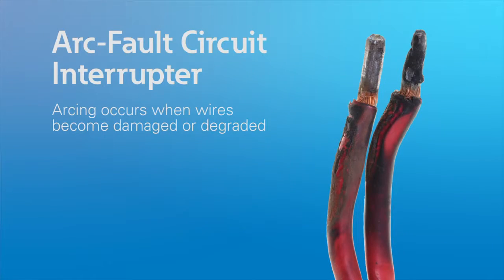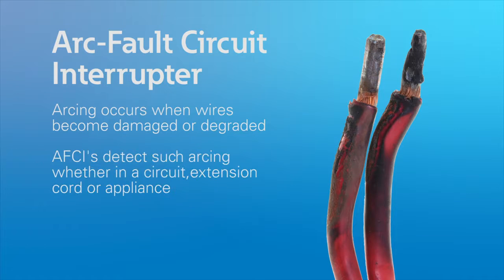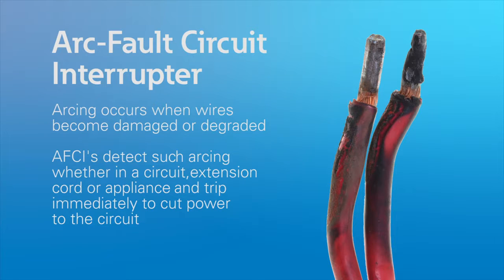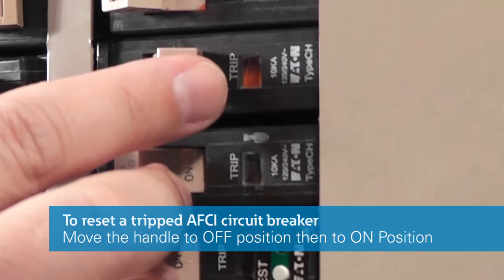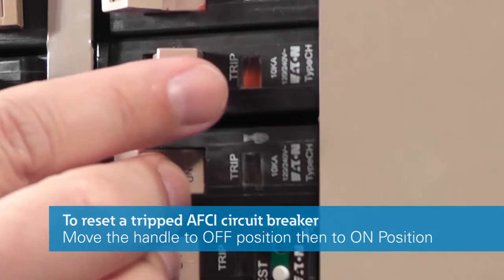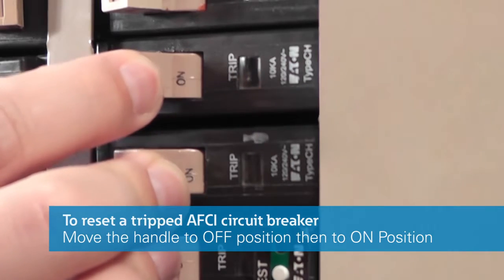Arcing occurs when wires become damaged or degraded. A high-temperature electrical arc can jump between two wires and cause surrounding material to ignite, starting an electrical fire. AFCIs detect such arcing whether in a circuit, extension cord, or appliance, and trip immediately to cut power to the circuit. To reset a tripped AFCI circuit breaker at the load center, move the breaker handle all the way to the off position and then back to the on position.